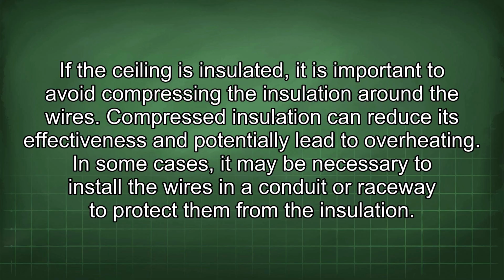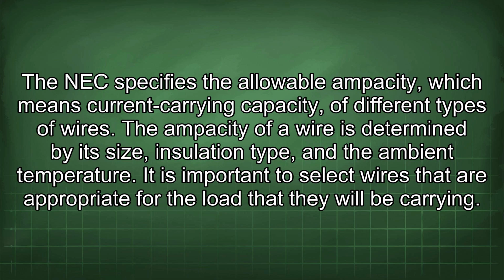Compressed insulation can reduce its effectiveness and potentially lead to overheating. In some cases, it may be necessary to install the wires in a conduit or raceway to protect them from the insulation. The NEC specifies the allowable ampacity, which means current carrying capacity, of different types of wires. The ampacity of a wire is determined by its size, insulation type, and the ambient temperature.